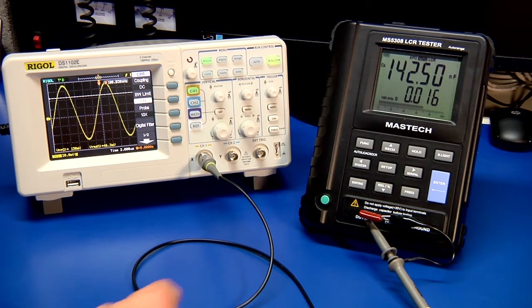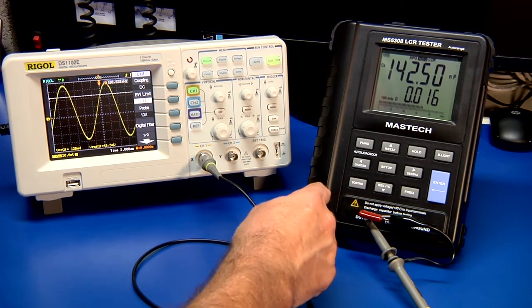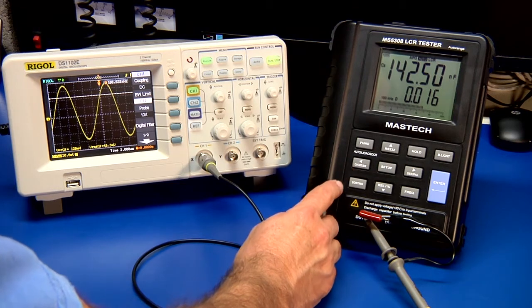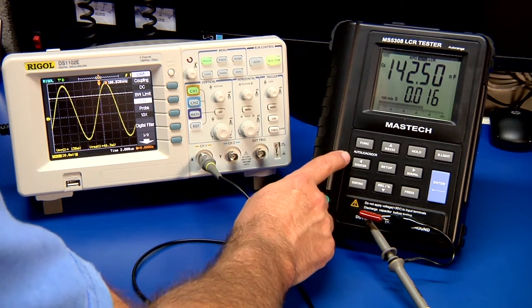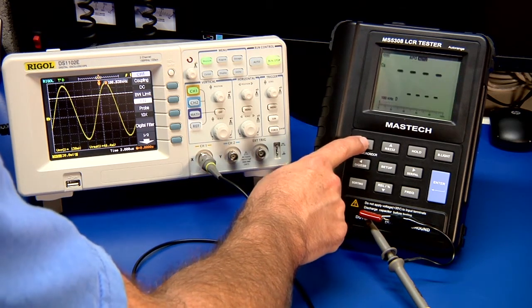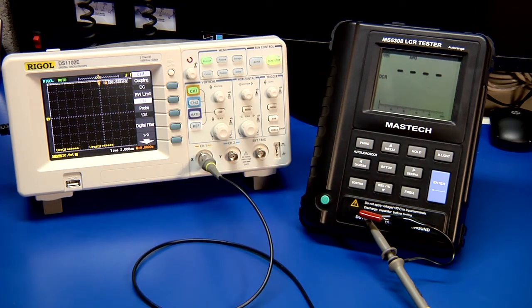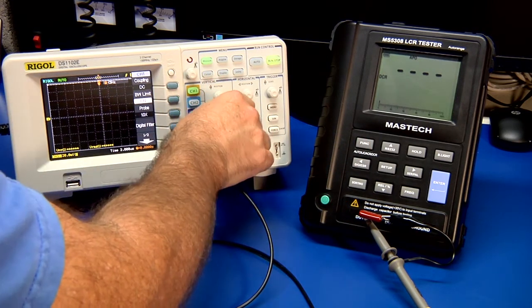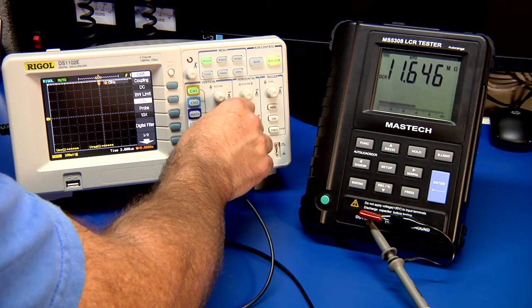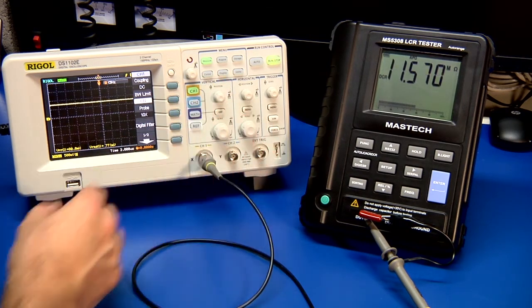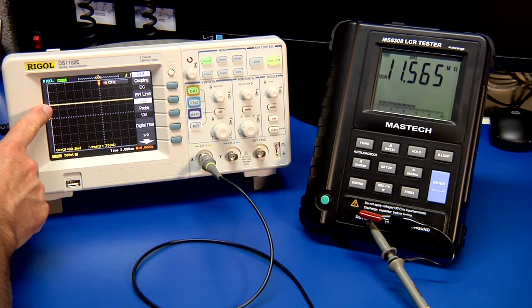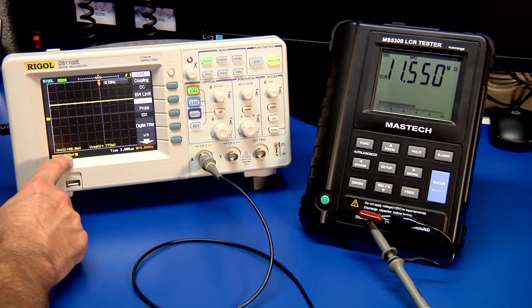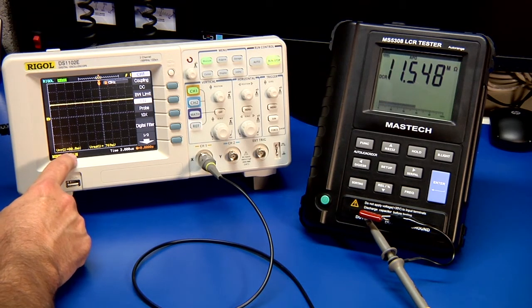We can also check if we're trying to measure DC, even though there's a capacitor, just as a quick example, we can go to DC, and again, it takes a long time for it to set up.